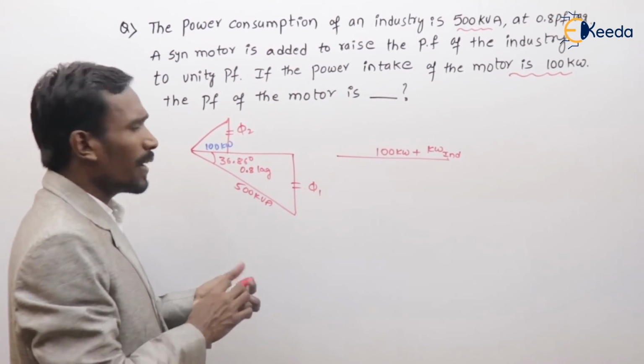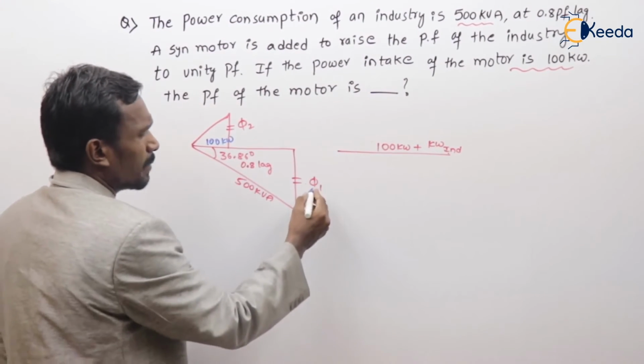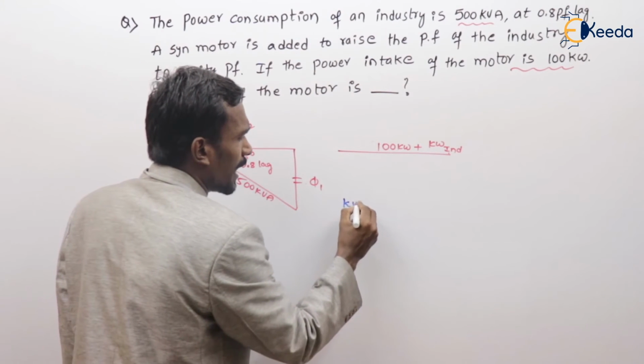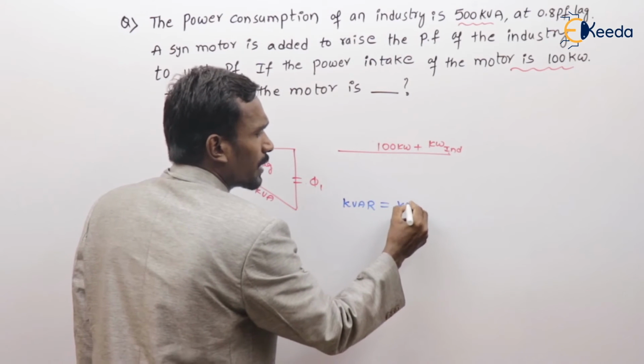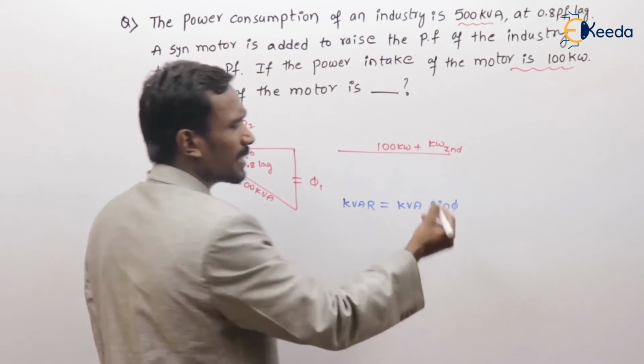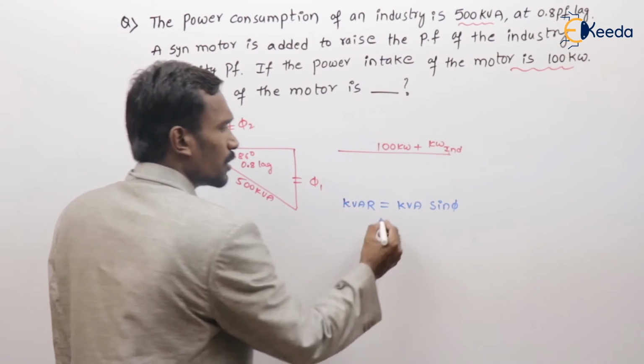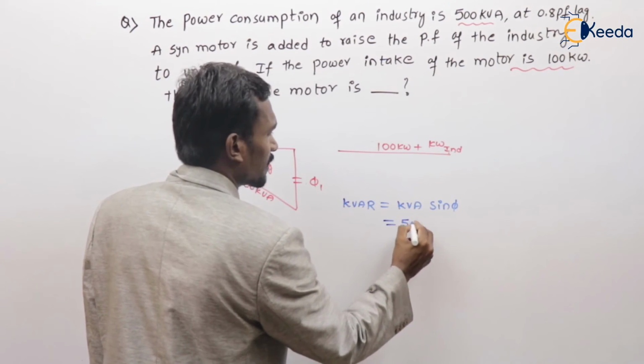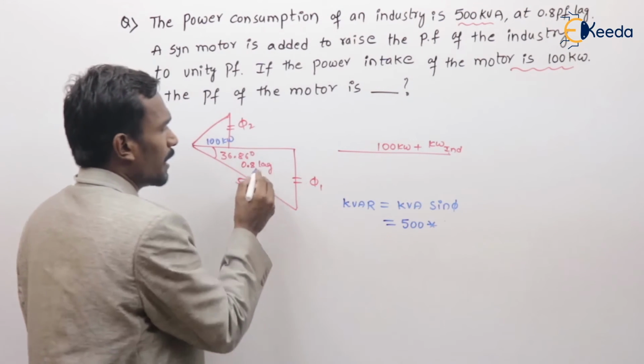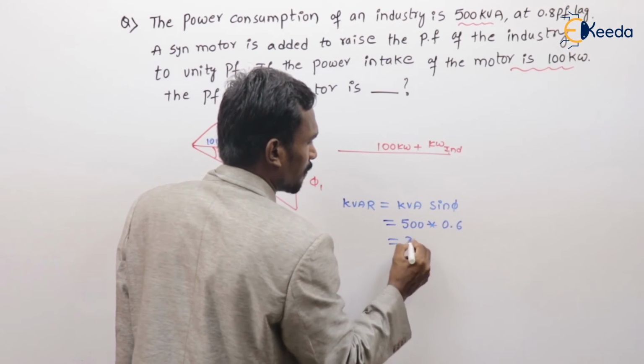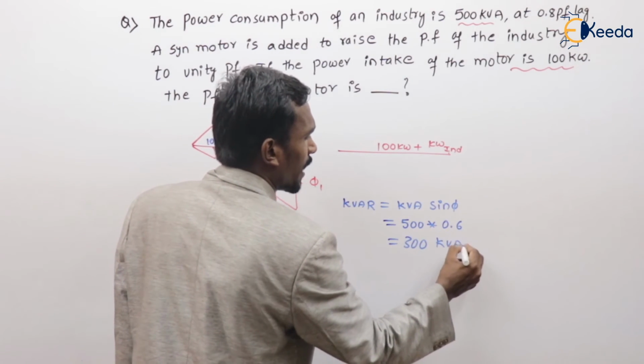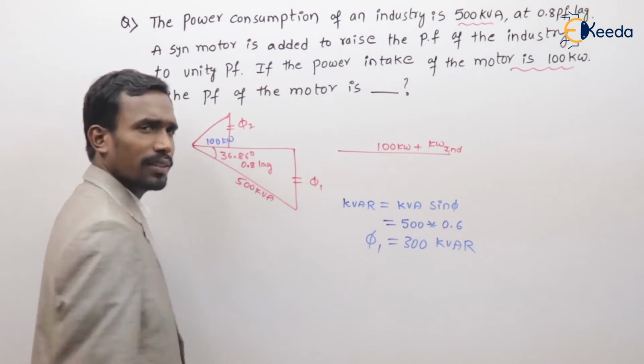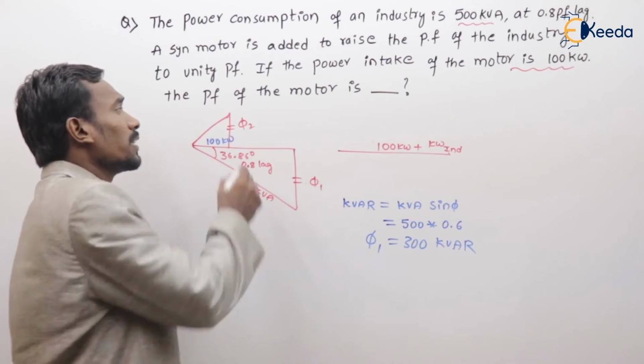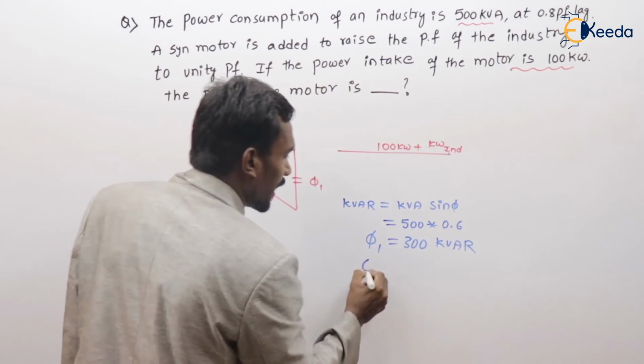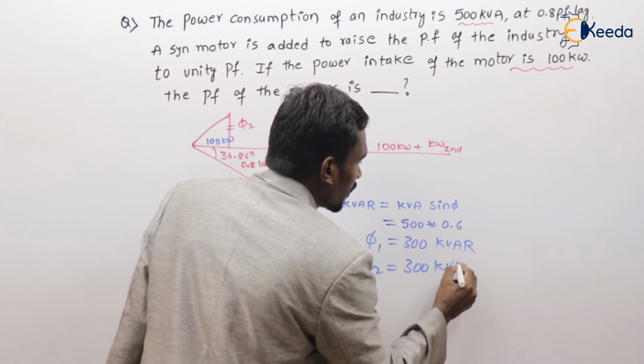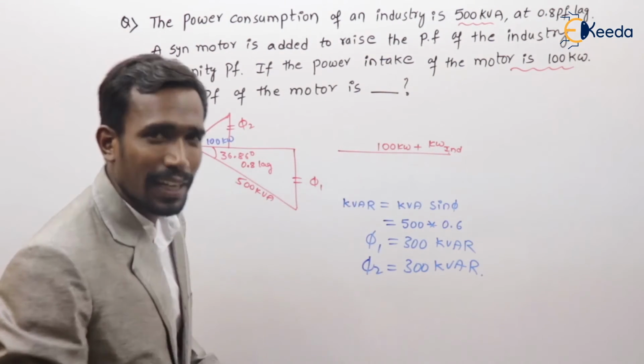Now tell me, what is Q1? Actually we have kVA, I want kVAR. kVAR is equal to kVA into sine phi. We know this already, right? So tell me, what is the value of kVA? kVA is 500 multiplied with sine phi. If cos phi is 0.8, sine phi is 0.6, nothing but 300 kVAR. 300 kVAR is phi 1. When this is 300 kVAR, this also must be 300 kVAR. Then the power factor is unity.